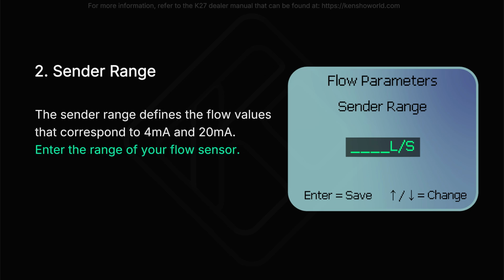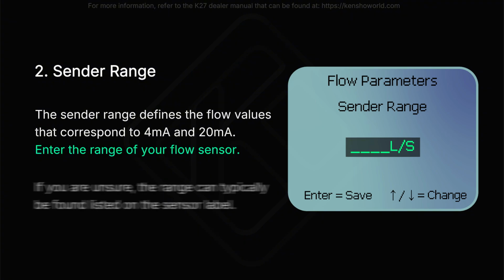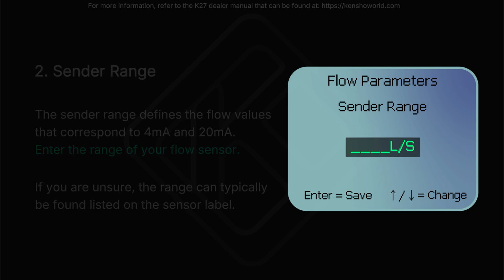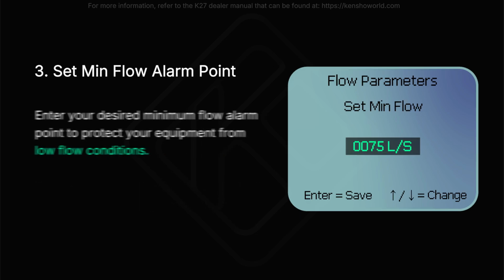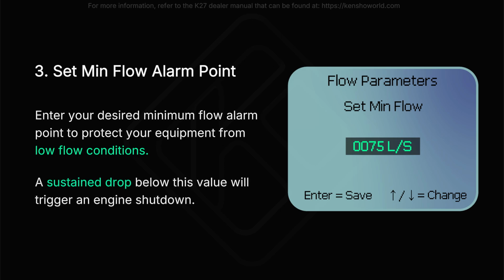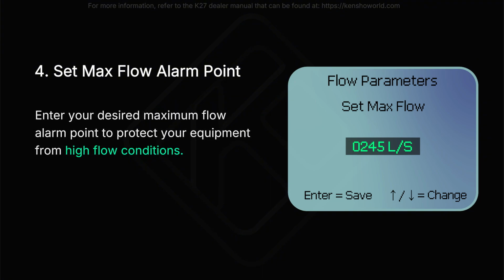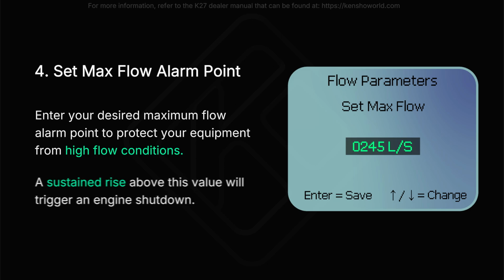The sender range defines the flow values that correspond to 4 mA and 20 mA. Enter the range of your flow sensor. If you are unsure, the range can typically be found listed on the sensor label. Enter your desired minimum flow alarm point to protect your equipment from low flow conditions. A sustained drop below this value will trigger an engine shutdown. Enter your desired maximum flow alarm point to protect your equipment from high flow conditions. A sustained rise above this value will trigger an engine shutdown.